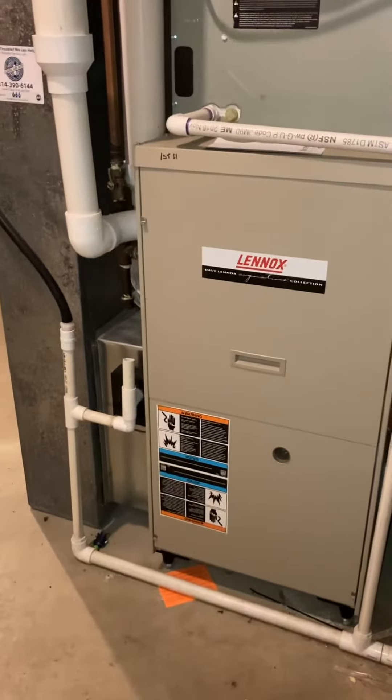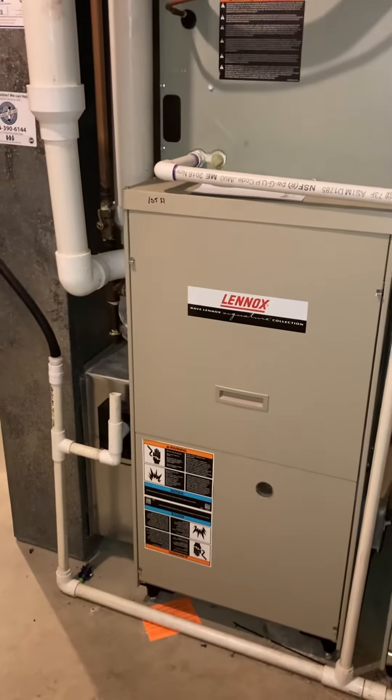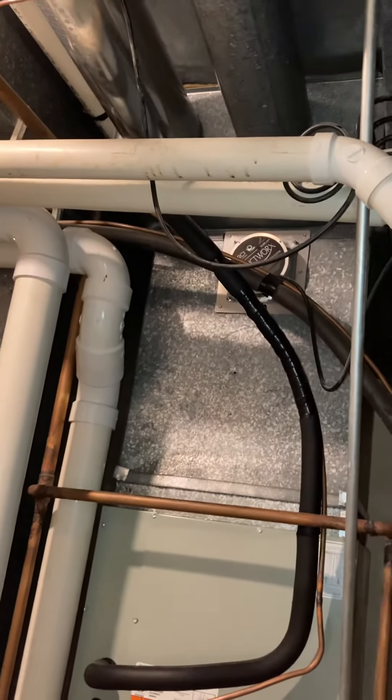You can see all the PVC greens — this is a C-width 90,000 BTU furnace. The weird thing is it's got a three-ton drive and it's connected up to a four-ton air conditioner, so we know that's not right. Basically take everything out.